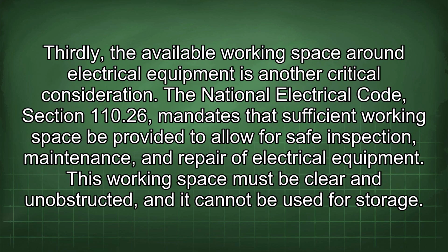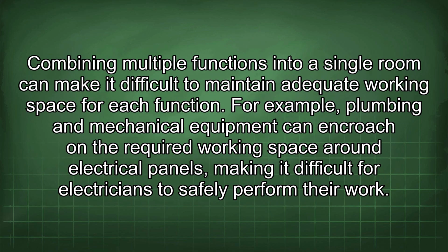Thirdly, the available working space around electrical equipment is another critical consideration. The National Electrical Code, Section 110.26, mandates that sufficient working space be provided to allow for safe inspection, maintenance, and repair of electrical equipment. This working space must be clear and unobstructed, and it cannot be used for storage. Combining multiple functions into a single room can make it difficult to maintain adequate working space for each function. For example, plumbing and mechanical equipment can encroach on the required working space around the electrical panels, making it difficult for electricians to safely perform their work.